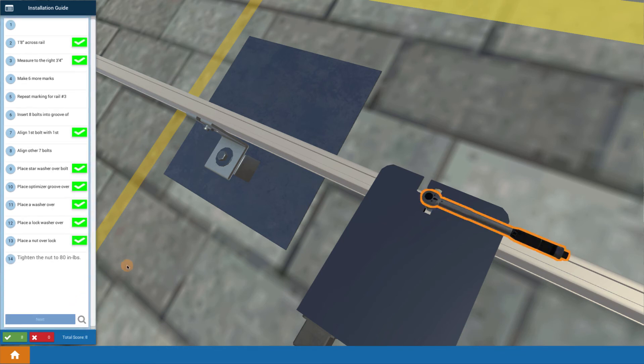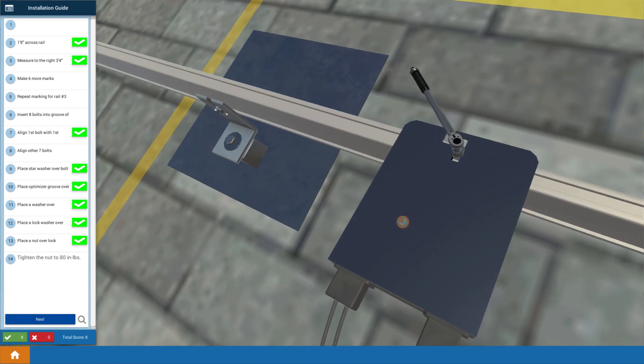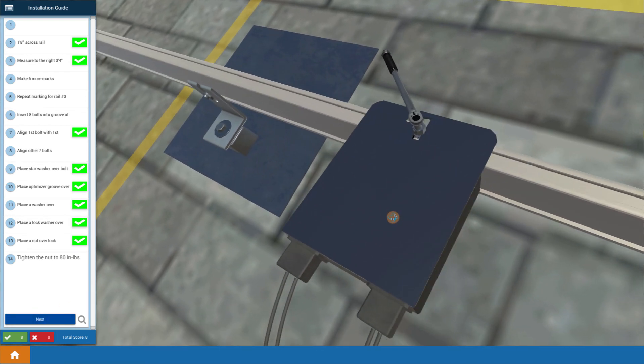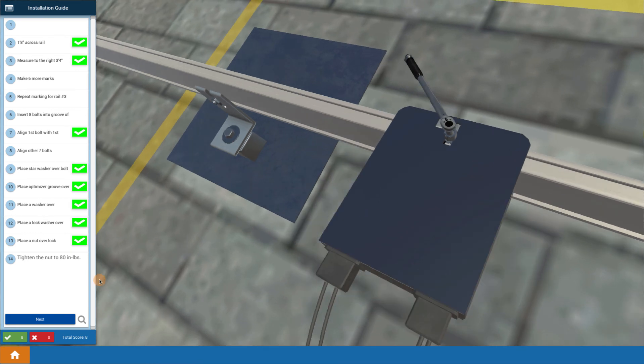And then you'd use a torque wrench. Click on it to tighten it to manufacturer specs. In this case, 80 inch pounds to make that a proper torquing down of that nut. You want that properly torqued so that it's not loose and going to come loose and fall apart and not too tight so it's going to strip the bolt.